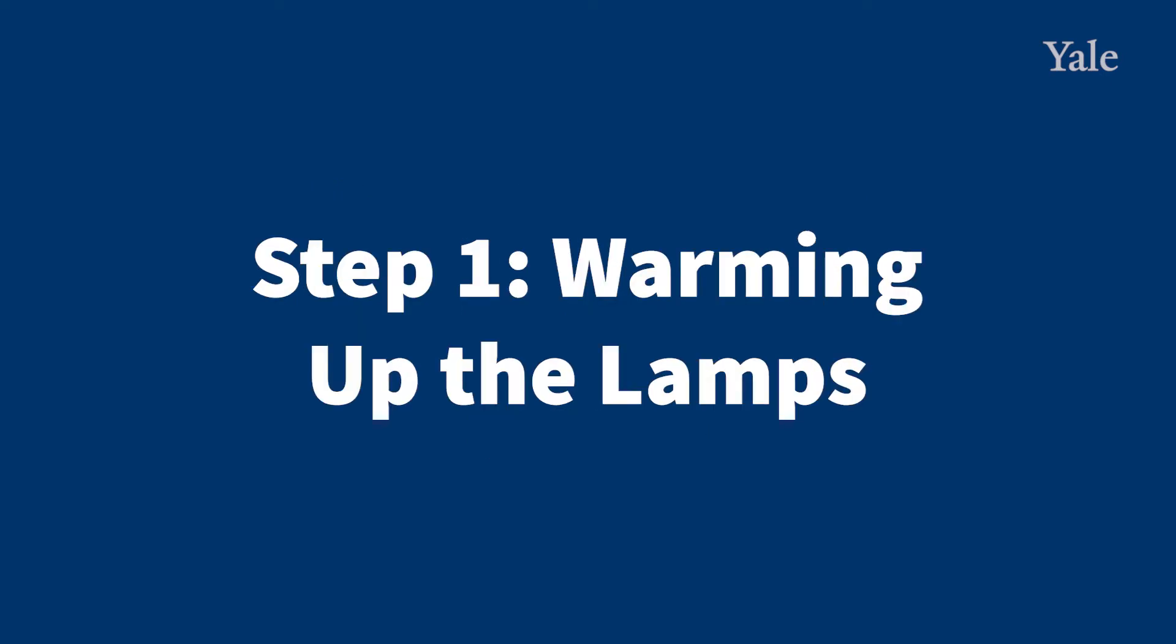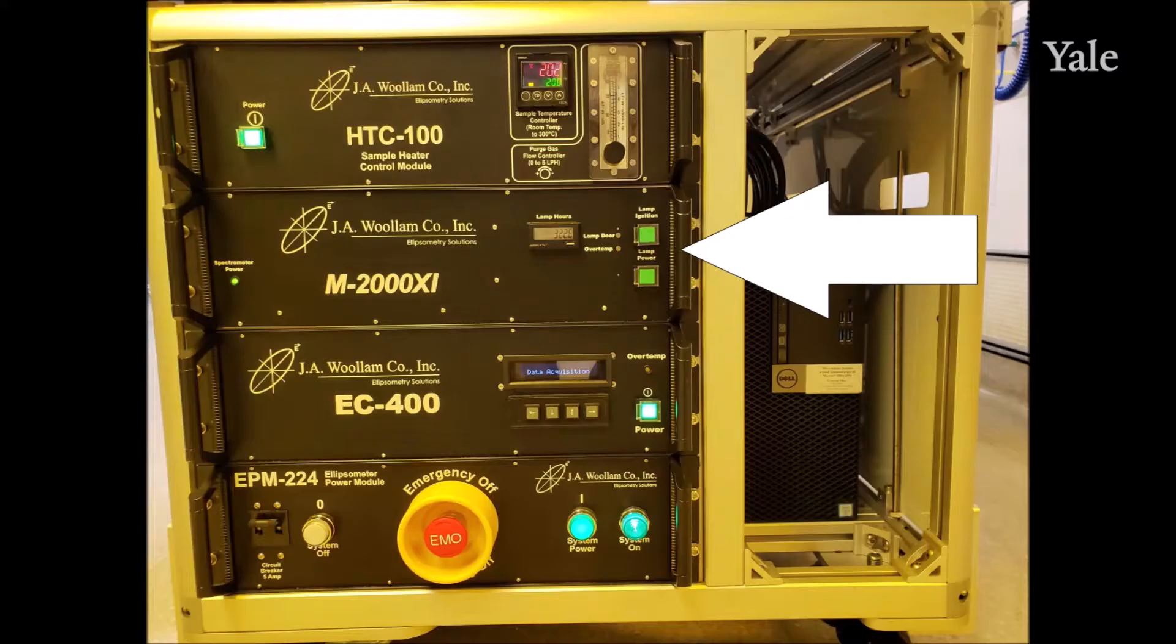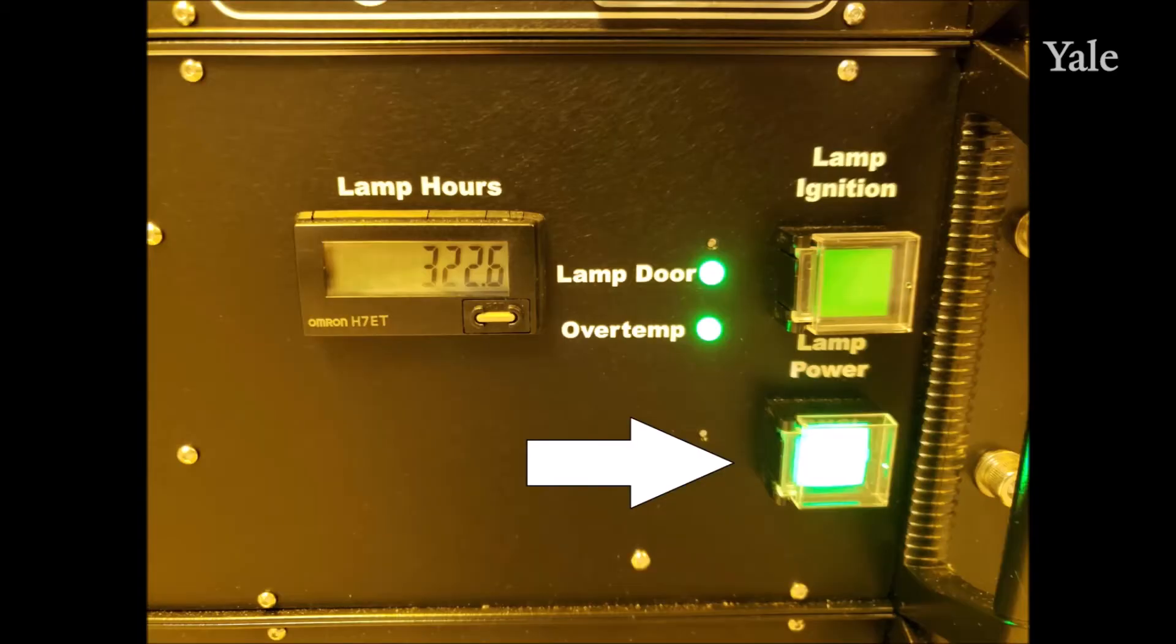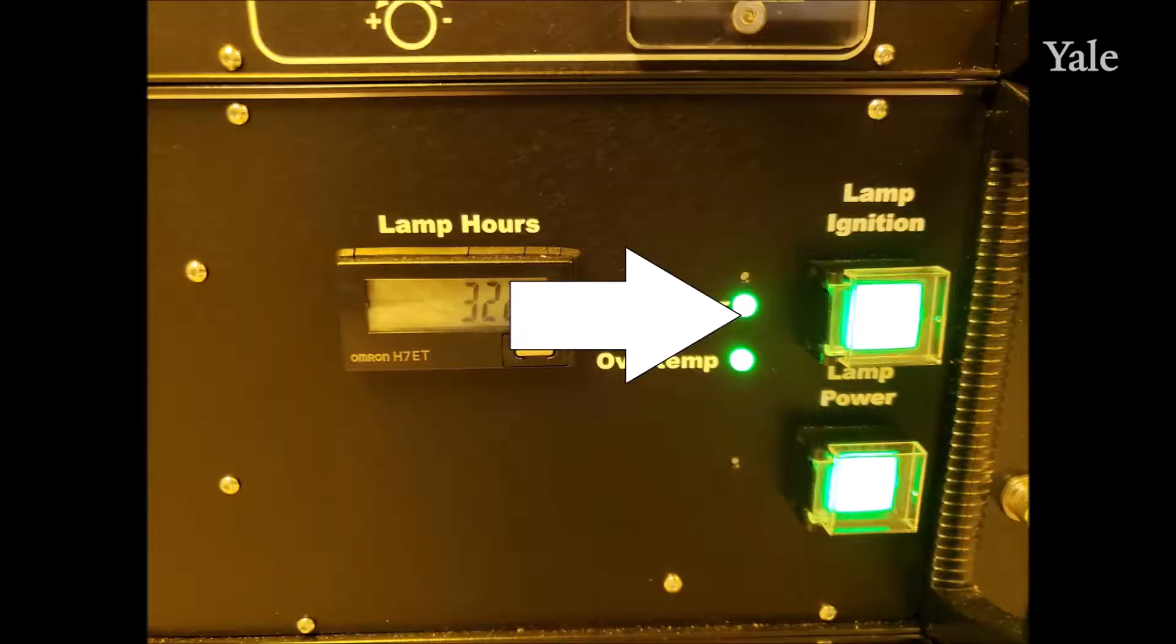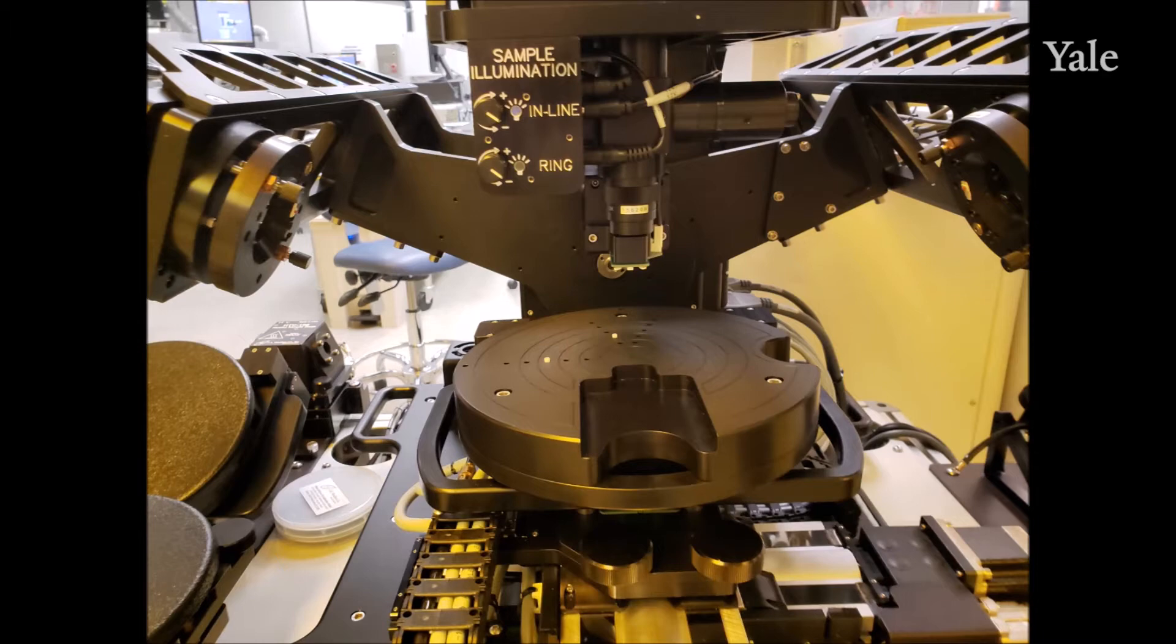Step 1: Warming up the lamps. When you first come to the tool, go to the lamp controls on the front panel, press the lamp power button, and then press the lamp ignition button. Wait up to 15 minutes for the lamp to stabilize and place your sample on the tool stage.